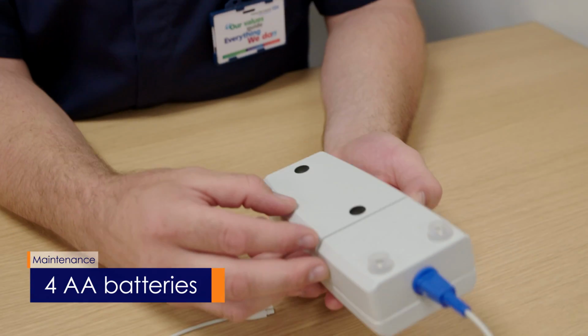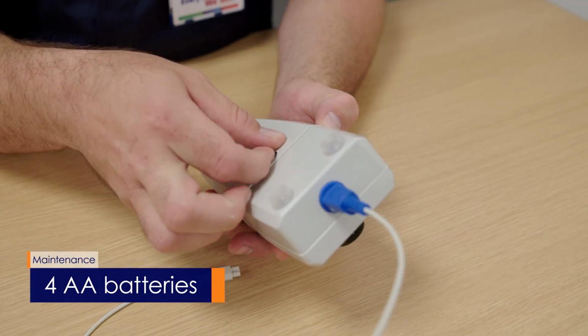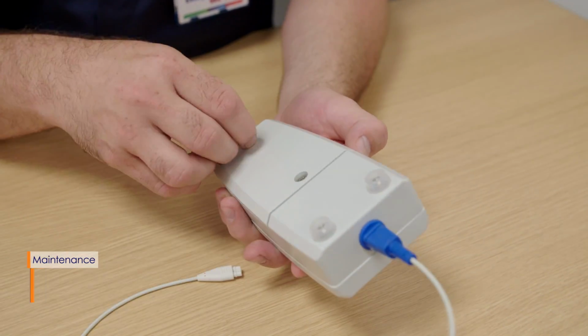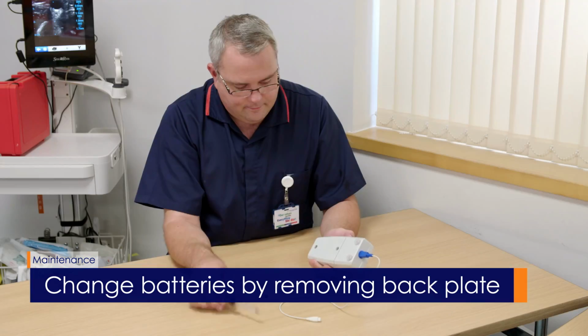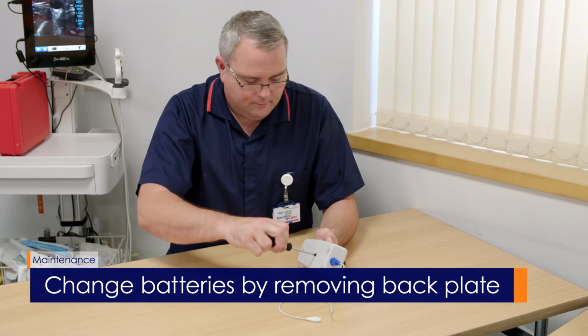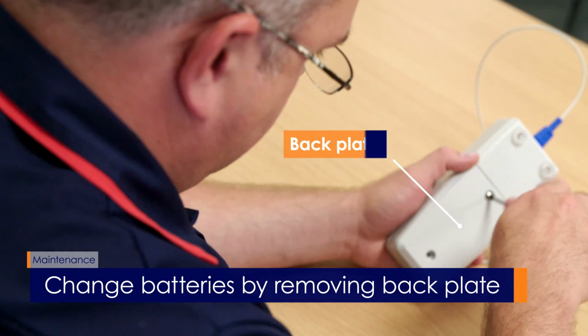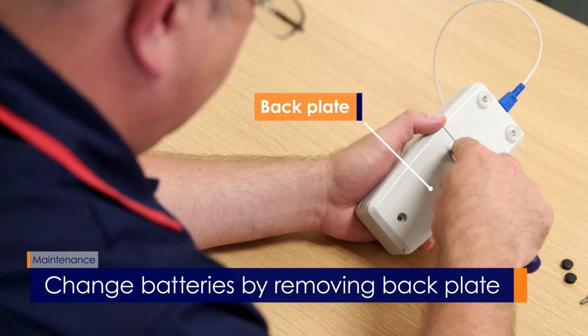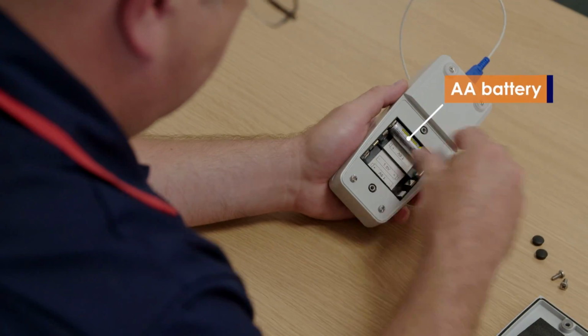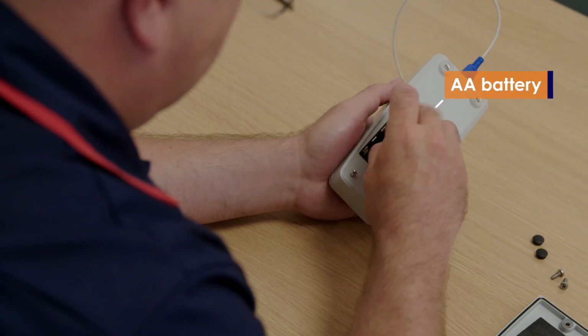The device uses 4 AA batteries, which should last for a minimum of 180 minutes of stimulation. To change the batteries, remove the black caps on the back of the device. Take off the back plate using a Phillips screwdriver. Ensure the new batteries face the correct direction. The battery should be disposed of and replaced when the battery indicator is active.